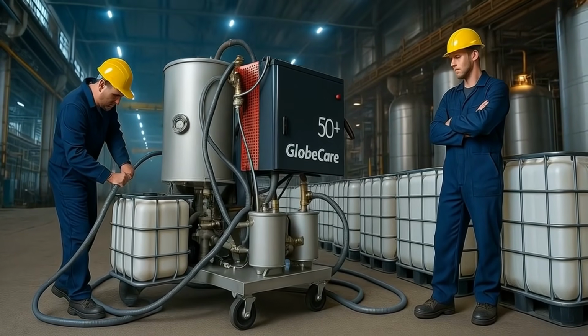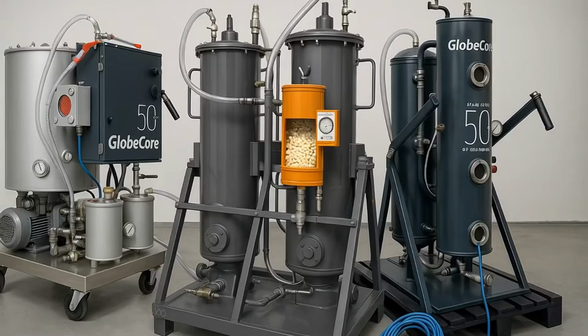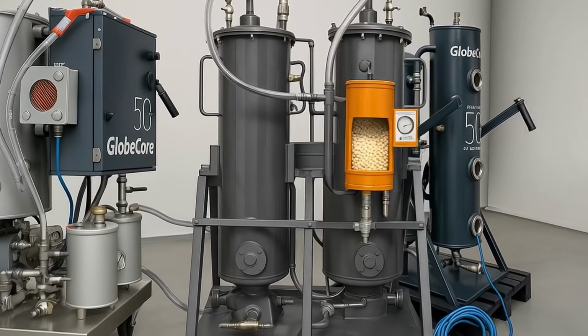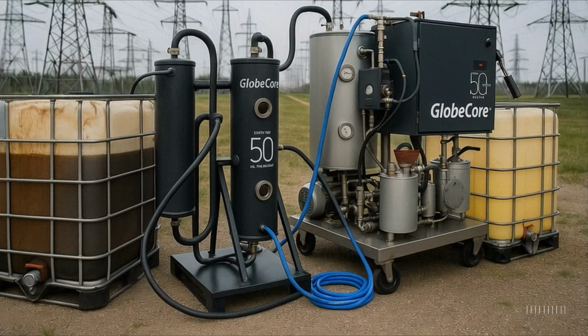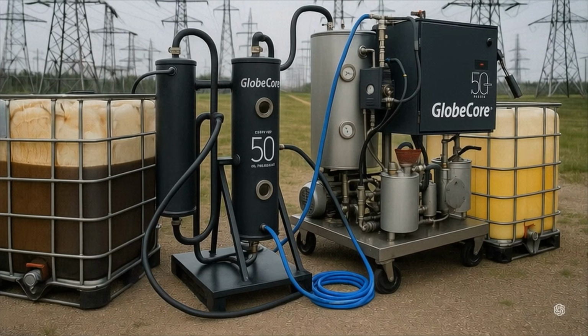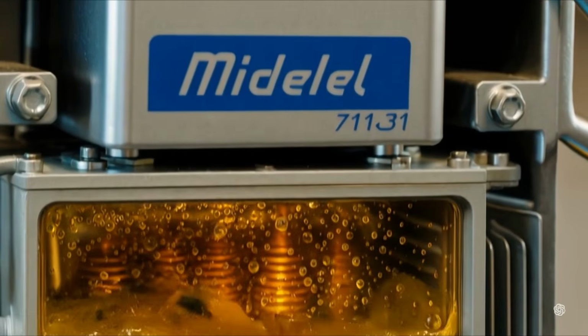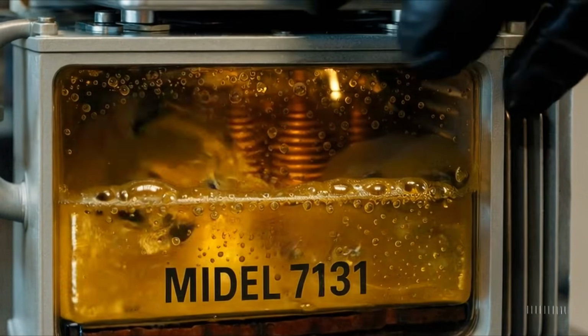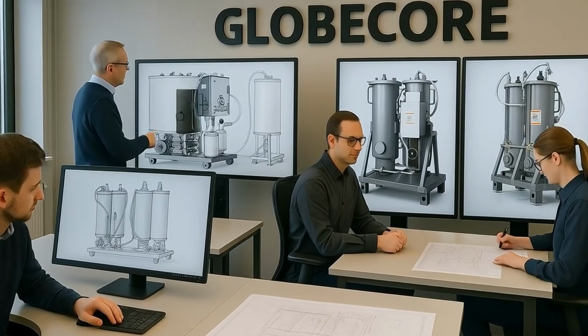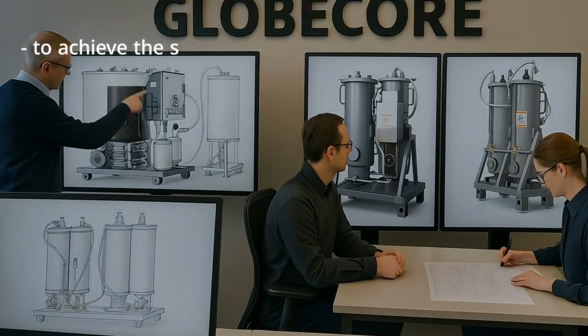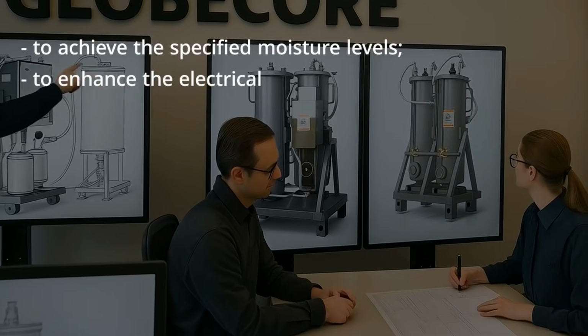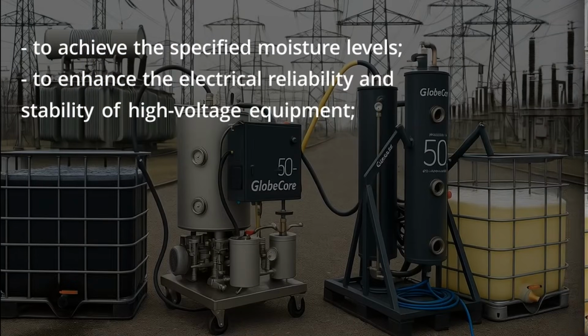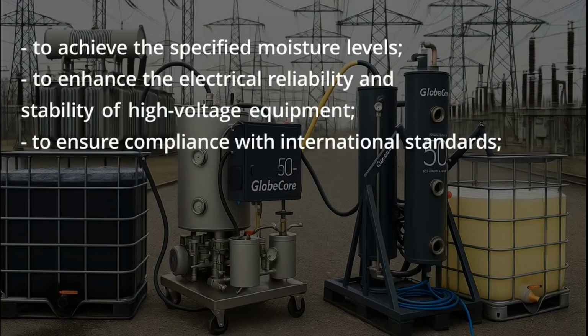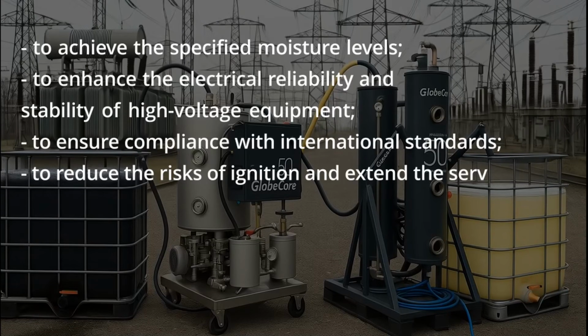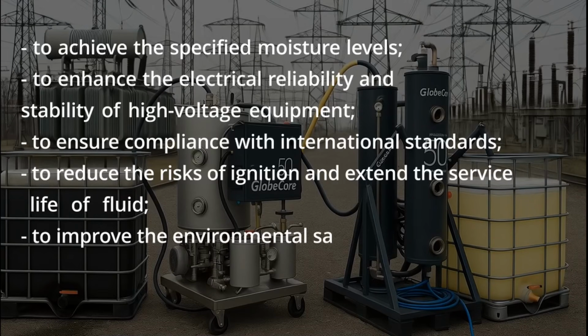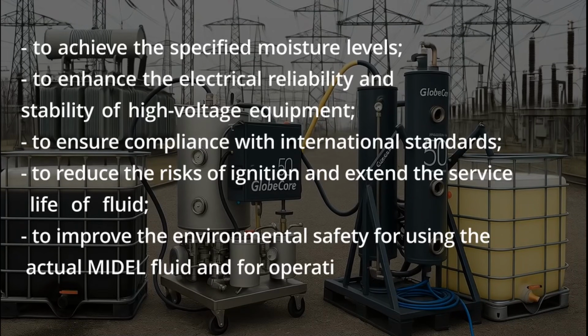The methods discussed above can be used individually or in combination, which allows the equipment to be flexibly adapted to specific conditions and requirements. Thus, depending on the initial state of MIDEL 7131 dielectric fluid, GlobeCore offers effective solutions that make it possible to achieve the specified moisture levels, to enhance the electrical reliability and stability of high-voltage equipment, to ensure compliance with international standards, to reduce the risks of ignition and extend the service life of fluid, to improve the environmental safety for using the actual MIDEL fluid and for operating the equipment wherein it is used.